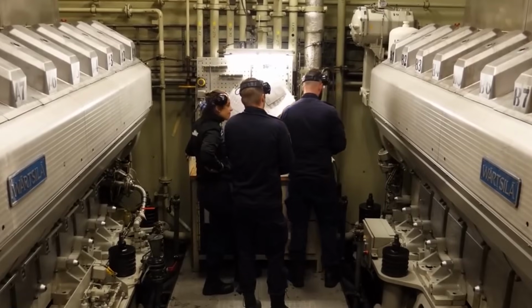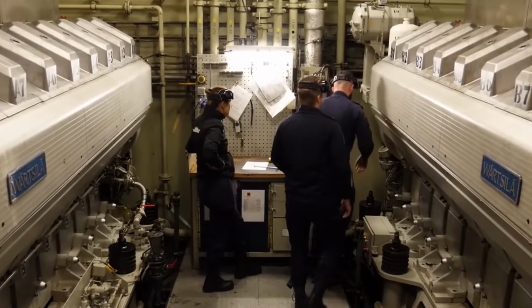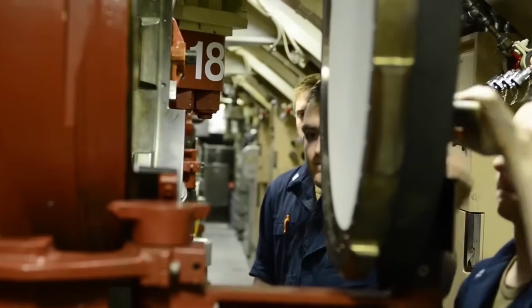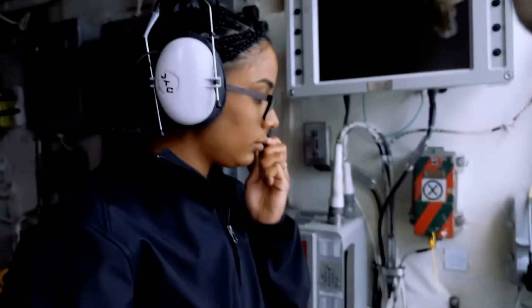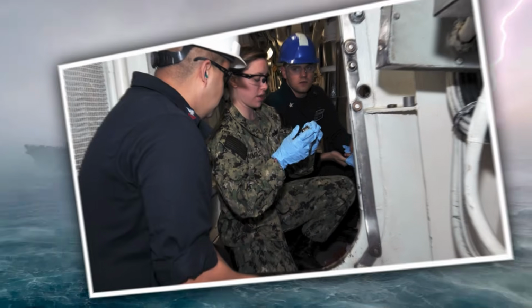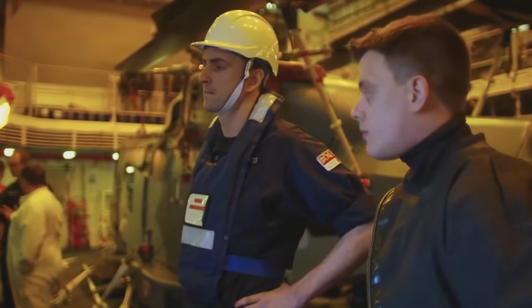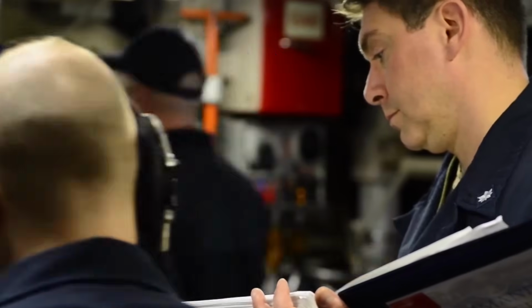You verify flow, not just that a motor spins. You watch temperatures and vibration as machinery wakes up. You listen for the sound you remember from a healthy machine. You watch for pressure drift that says air is trapped or a strainer is loading. Then you communicate limits. What is fully normal? What is being watched? What is still restricted? Everything is logged so the next watch does not inherit mystery.